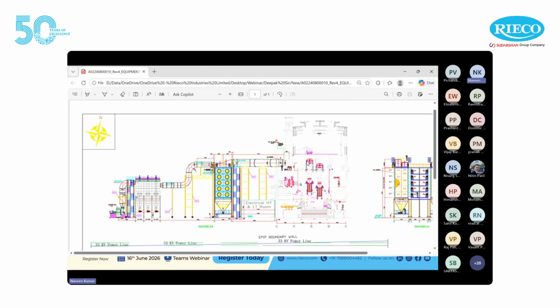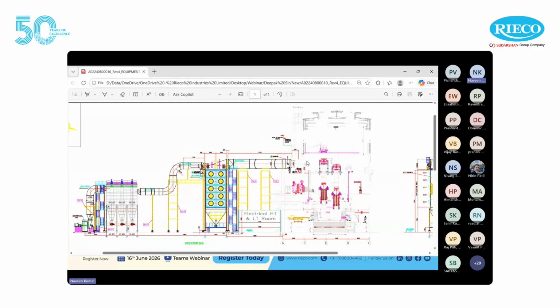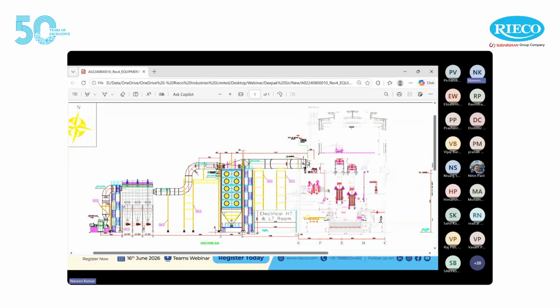This is a typical layout where, as I showed there, the submerged arc furnace has one tapping duct from the submerged arc top release, which first flows to the air-to-air heat exchanger, where we also have the axial flow fans. Based on the inlet temperature, we can optimize the power consumption by the number of active axial flow fans running.